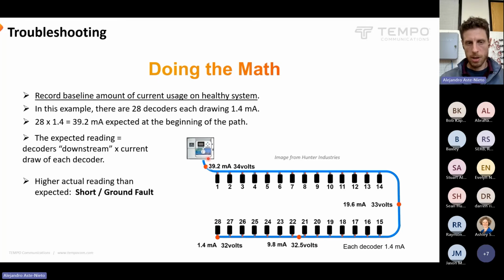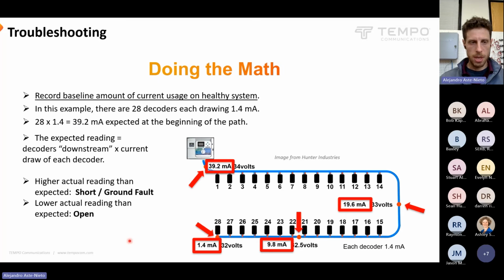If we take a higher number here at the beginning, we know that the problem somewhere on this wire path is a short or a ground fault, and there's extra current being used. If it's lower, then we have an open somewhere. We have a break somewhere, or we have offline decoders. So take measurements at different points and compare them to what you're expecting to tell you what kind of problem and where it is.